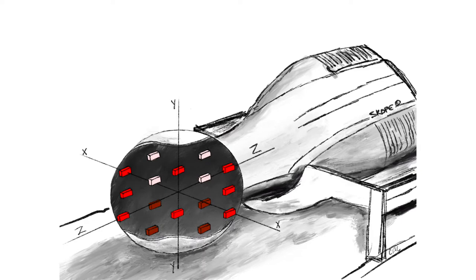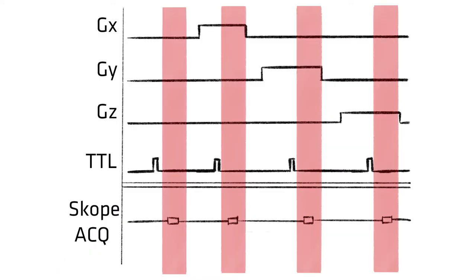Skope field cameras must first be calibrated to establish the locations of the individual field probes in gradient space before the camera can be used to monitor field dynamics. We use four acquisitions to calibrate the position and static off-frequency resonance of each field probe. The first repetition is acquired without any activity of the scanner and measures the local field at that position. Then, we play three acquisitions, each with a 2.5 millitesla per meter gradient on one of each of the three physical axes.